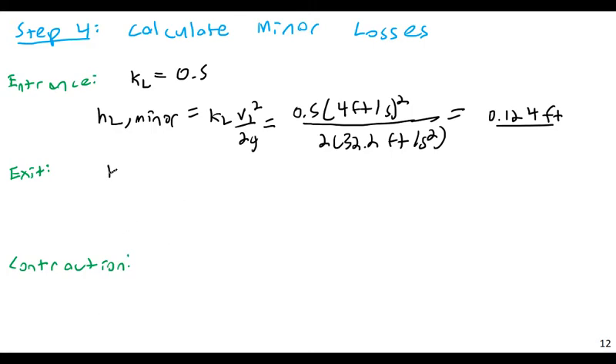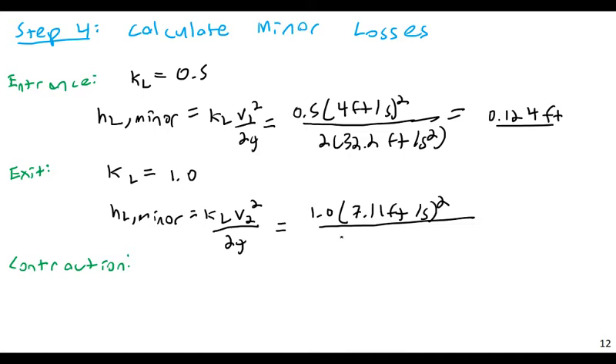And here, from another table in the book with an exit on it, I get that KL is equal to 1.0, and for this, HL minor is equal to KL, and this time I'm going to use V2, because it's the exit, and it's connected to the second piece of pipe, V2 squared divided by 2G, equals then 1.0 times 7.11 feet per second quantity squared divided by 2 times 32.2, and I get a minor loss here of 0.785 feet.